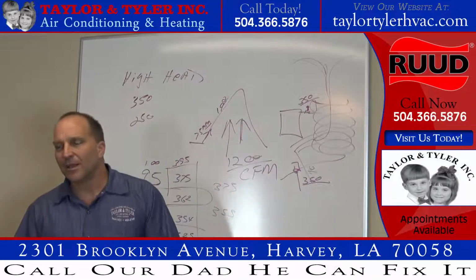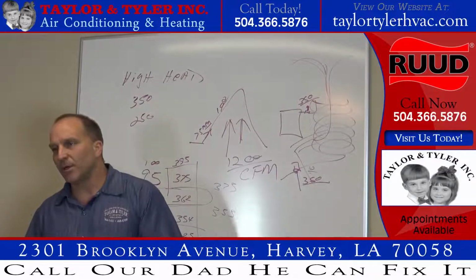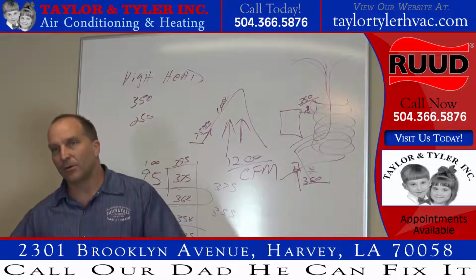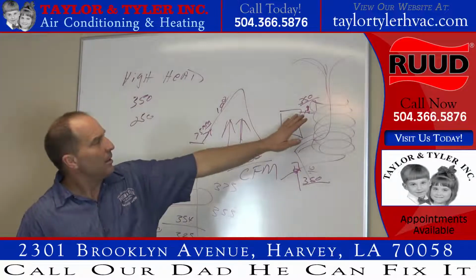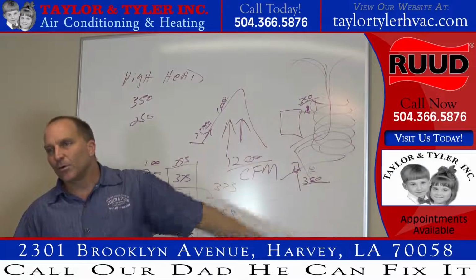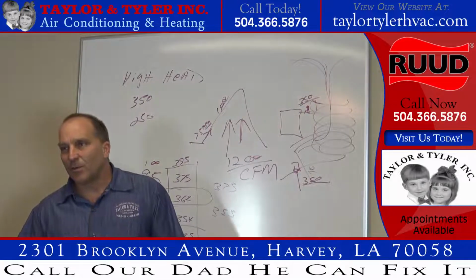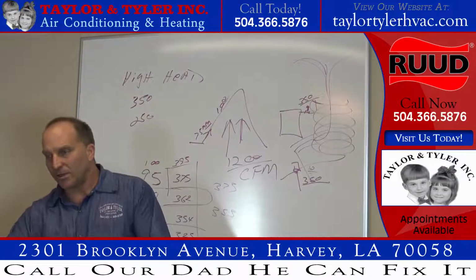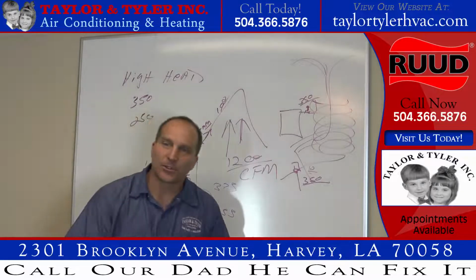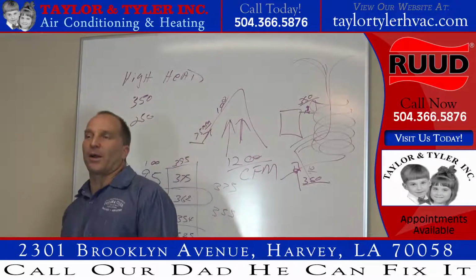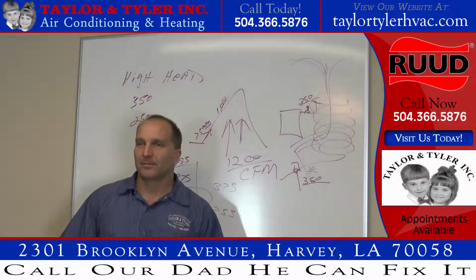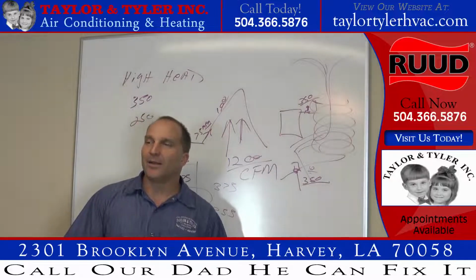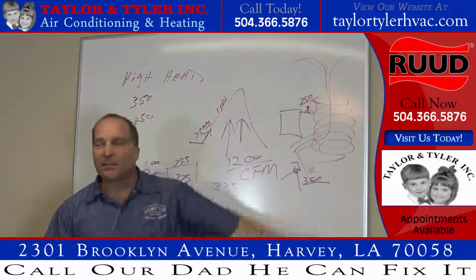So when I put my gauge on the system and I am looking for a 350 pound head pressure, this was an old R22 system years ago when this happened, probably, I don't know, 20 years ago, okay? So I was looking for about a 225 pound head pressure in the inside. So when I turn that system on, gauge runs down to the bottom, I watch my head pressure and it goes 500-600 pounds of pressure in it. Now I know why I got a restriction in my condenser.